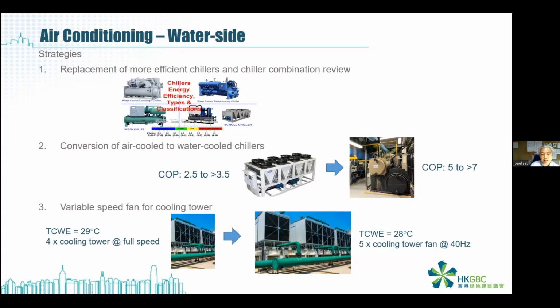The second one is to convert the air cool system into the water cool system. Most likely in Hong Kong, we do not convert air cool directly to indirect seawater cool because it is too expensive, and the site has some constraints: it should be very near the seashore. But most likely we can use or add cooling towers in order to use freshwater cooling. This is quite common in Hong Kong, to do the conversion from air cool to water cool.